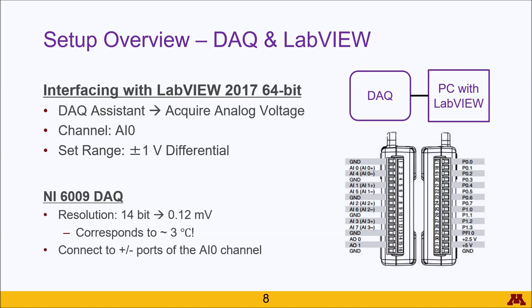For your reference, given the plus or minus one volt differential, 14-bit resolution corresponds to 0.12 millivolts as the minimum voltage that can be read. Given the sensitivity of roughly 41 microvolts per degree Celsius, this means the minimum temperature readable by the DAQ without amplification is 3 degrees Celsius — hence why we need that amplification.